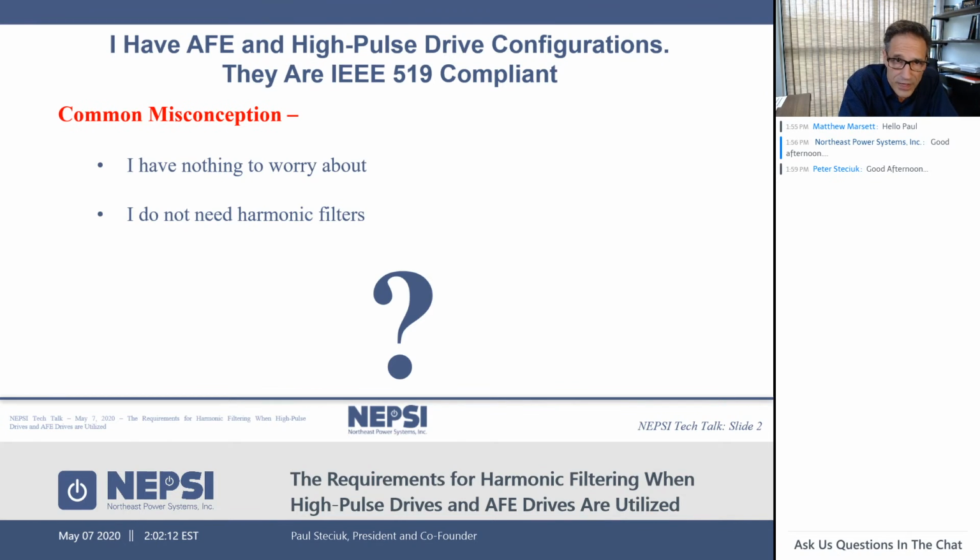So I often get this question when I get phone calls about high pulse drives and AFE type drives. Oftentimes the customers will say, hey, they're IEEE 519 compliant, I have nothing to worry about. They want to install power factor correction and they're going to install standard capacitor banks. And oftentimes they would say, hey, what's the big deal? I have AFE drives. They're compliant and I have nothing to worry about.